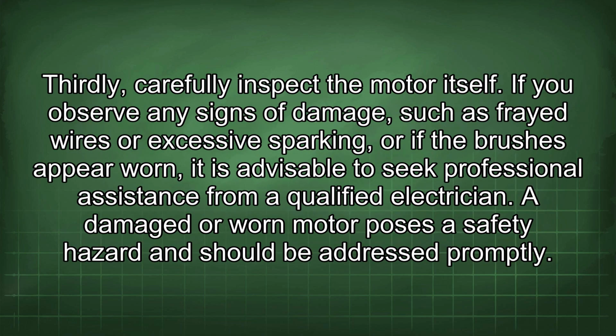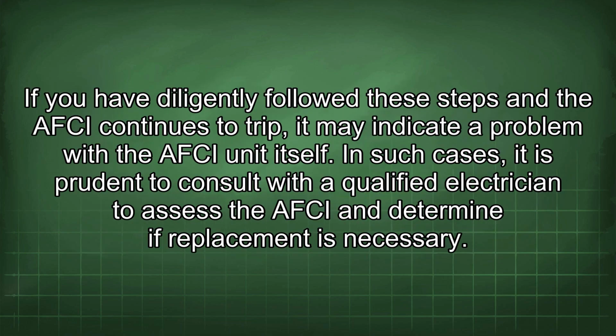Thirdly, carefully inspect the motor itself. If you observe any signs of damage, such as frayed wires or excessive sparking, or if the brushes appear worn, it is advisable to seek professional assistance from a qualified electrician. A damaged or worn motor poses a safety hazard and should be addressed promptly. If you have diligently followed these steps and the AFCI continues to trip, it may indicate a problem with the AFCI unit itself. In such cases, it is prudent to consult with a qualified electrician to assess the AFCI and determine if replacement is necessary.